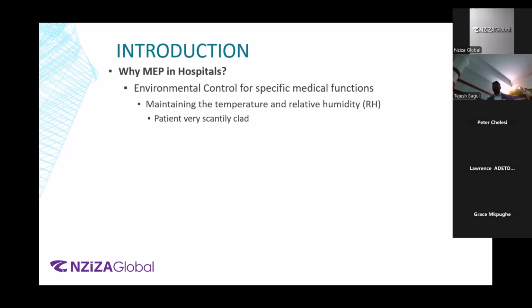Someone who is trying to recover from a disease or from some kind of illness, their heat rejection from their body will be amplified, because if the temperature in your rooms is too low, or if it is too high, then it will cause too much sweating, right? So for that reason, we need to make sure that the environmental control of different medical functions is properly set. We'll take a look into the ASHRAE 170 standard, which specifically gives us the temperature range and the relative humidity range. It will also give us the air change rates per hour. It is sometimes called ACH, sometimes ACPH as well. Air changes per hour, ACPH or ACH, all right?